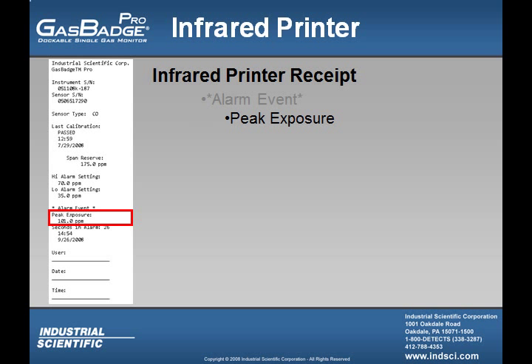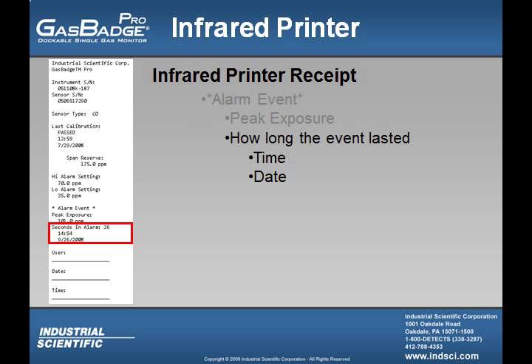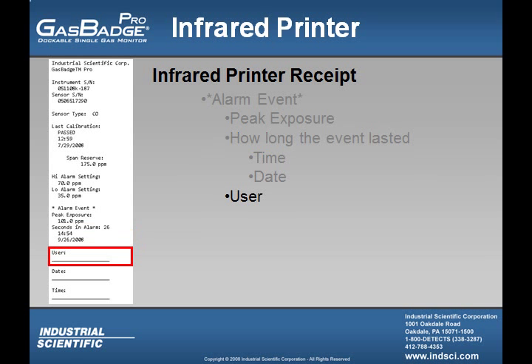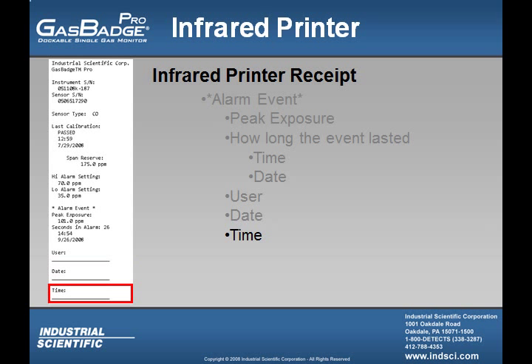The peak exposure line shows the user the highest peak the instrument saw during a particular alarm event. The receipt also shows how long the event lasted, as well as the date and time the alarm occurred. After that, the user can write their name or sign the receipt, verifying who printed it, as well as the date and time the receipt was printed.